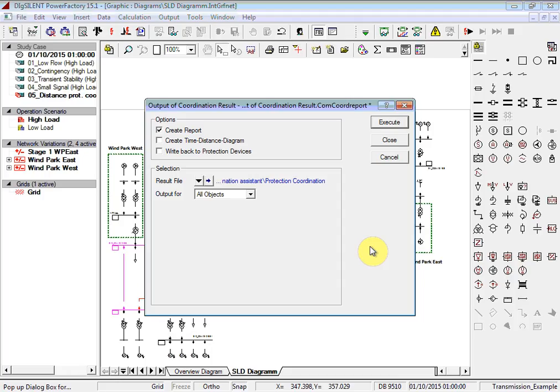Here we have 3 options. We can create a tabular report, we can create a time distance diagram, or we can choose to write back any results that we calculate to the protection devices which are installed. This option can only be used if you have actually installed protection devices in your network. First, let's create a report as well as to create the time distance diagrams. Choose the option Create Time Distance Diagram.